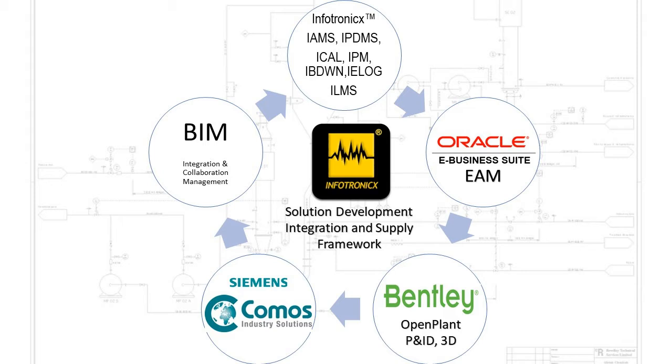Two: Infotronicx Smart Plant P&IDs and CMMS framework contain more information than their traditional predecessors. For example, when a pump is inserted into a P&ID within the Infotronicx Smart Plant P&IDs and CMMS framework environment, the software requires inlet and discharge sizes to be input so that the background database can track the piping into and out of the pump. The same holds true for most inline equipment and devices such as valves, flow meters, etc.